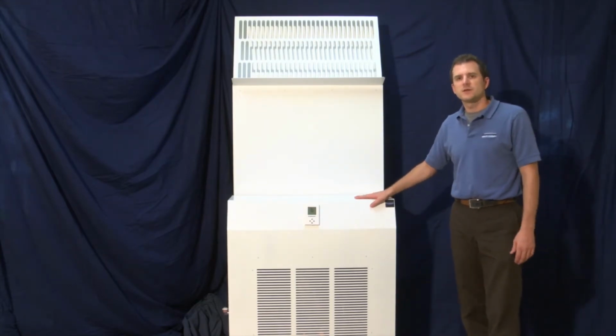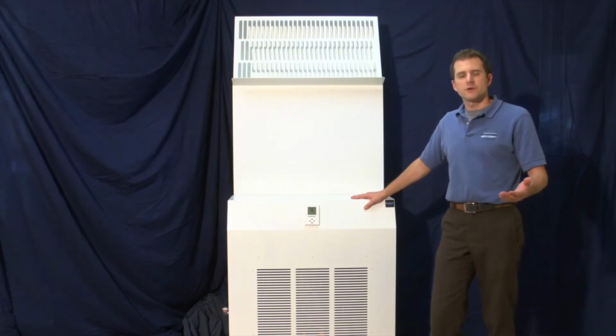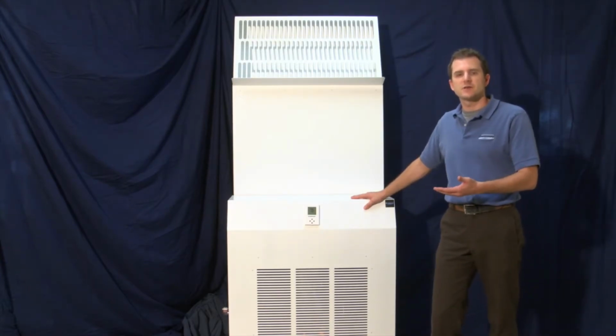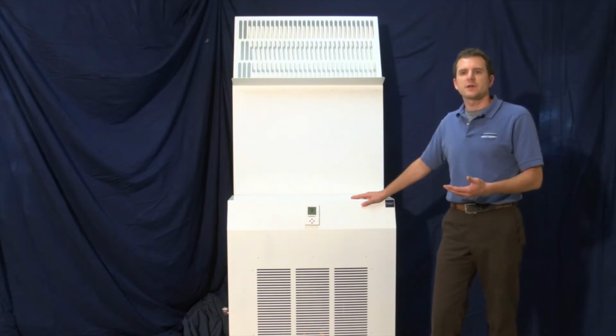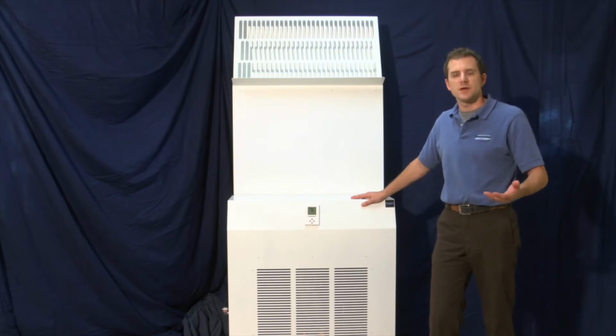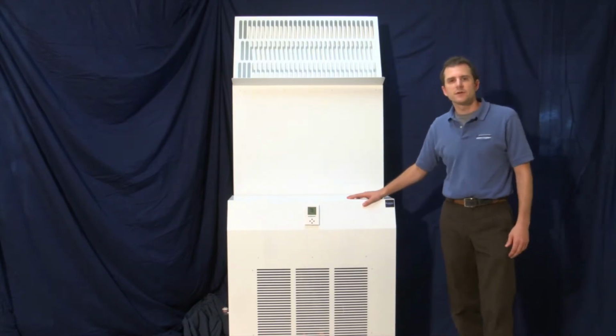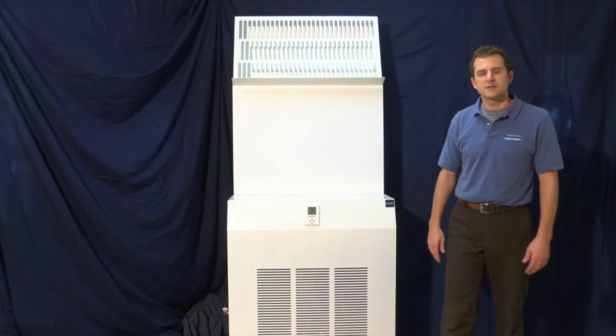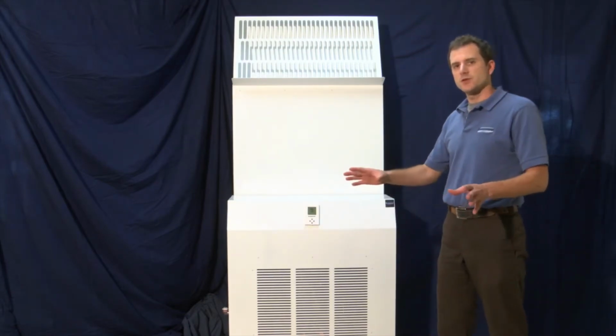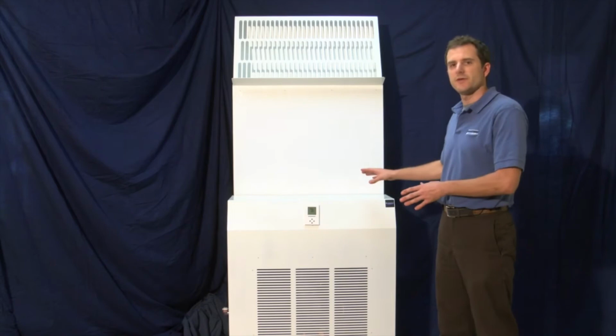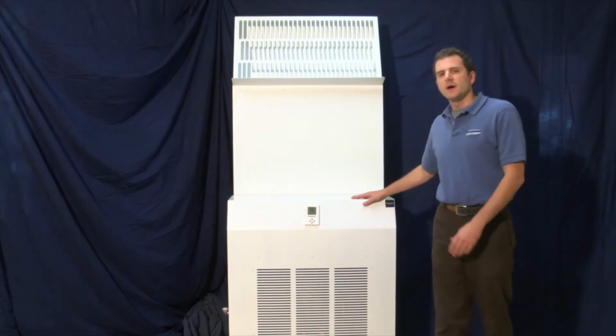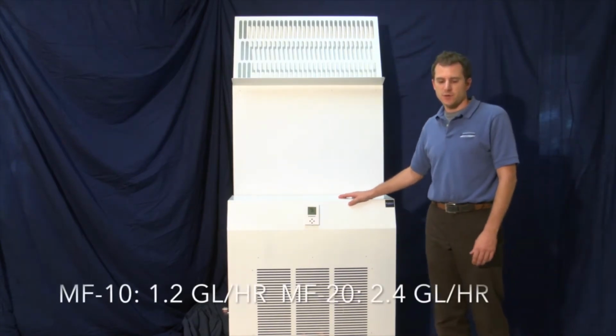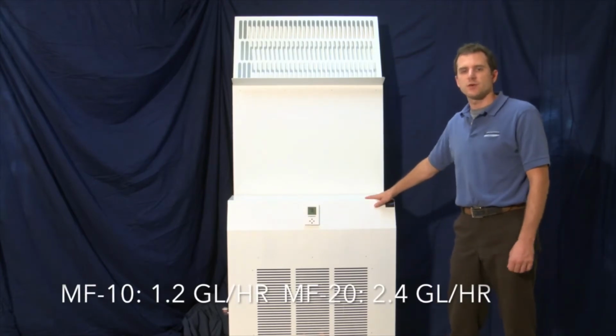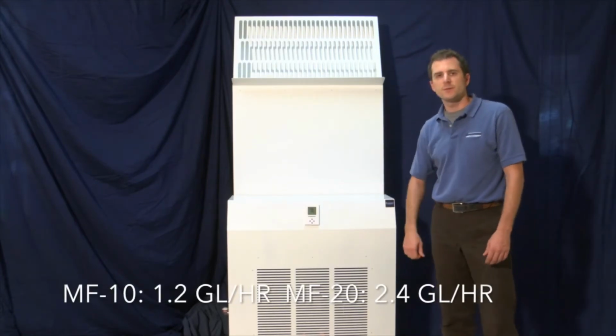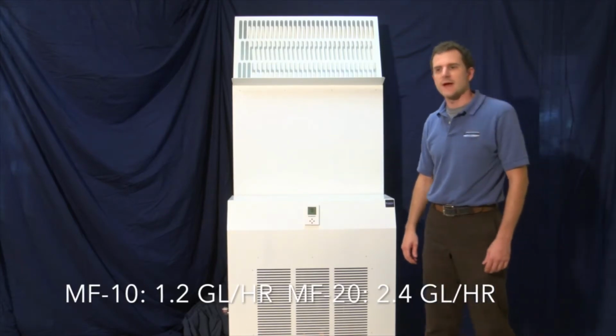Generally, the factory recommends treated water, an RO, reverse osmosis, or DI, deionized water source. Although there are certain applications with heavy organics in the air where treated water can harm you as much as help you. The most important thing to think about when choosing an RO or DI system is that the water treatment system can properly feed the humidifier with the right amount of water. The Mist-Free 10 is doing 10 pounds per hour, or about 1.2 gallons per hour. The Mist-Free 20 is doing 20 pounds per hour, or about 2.4 gallons per hour.